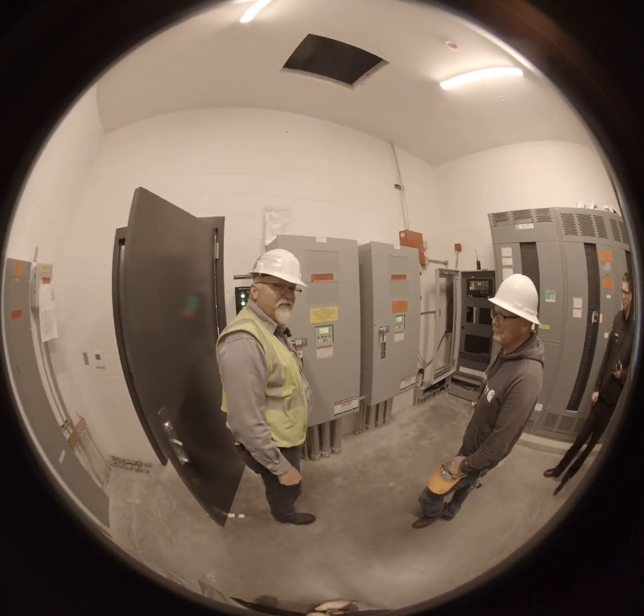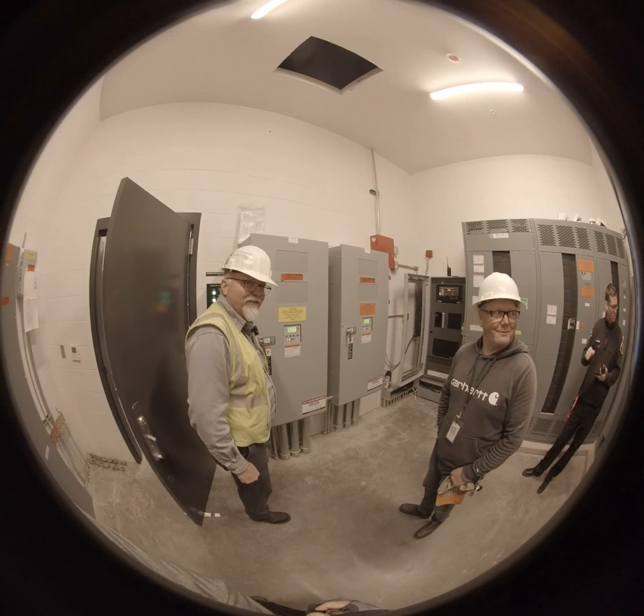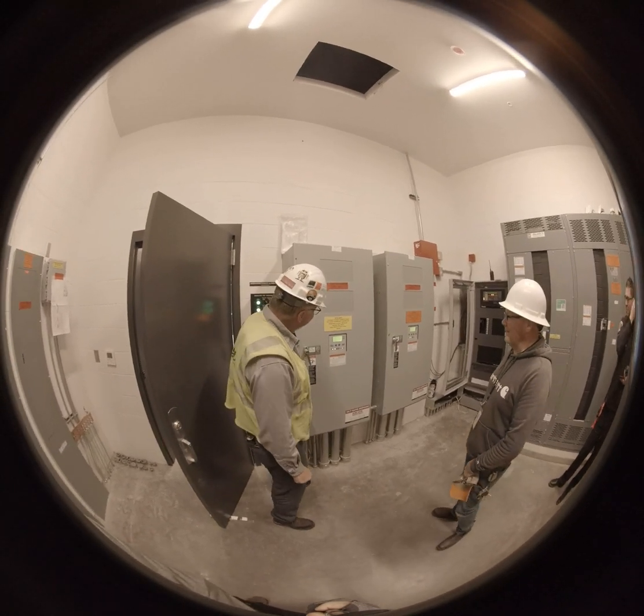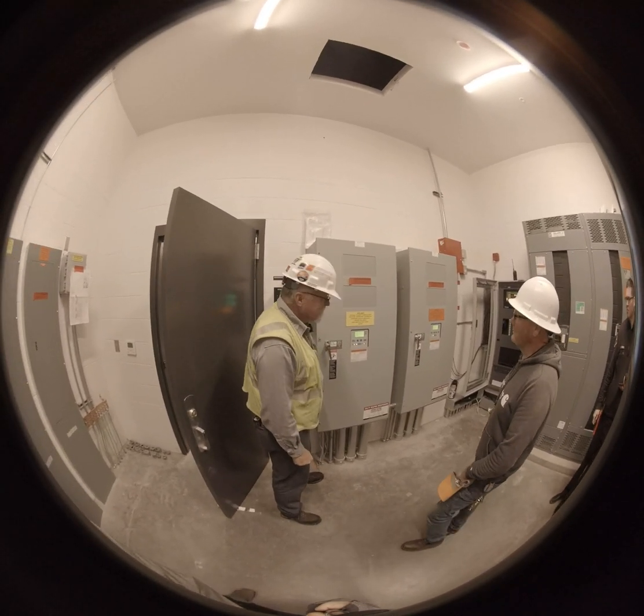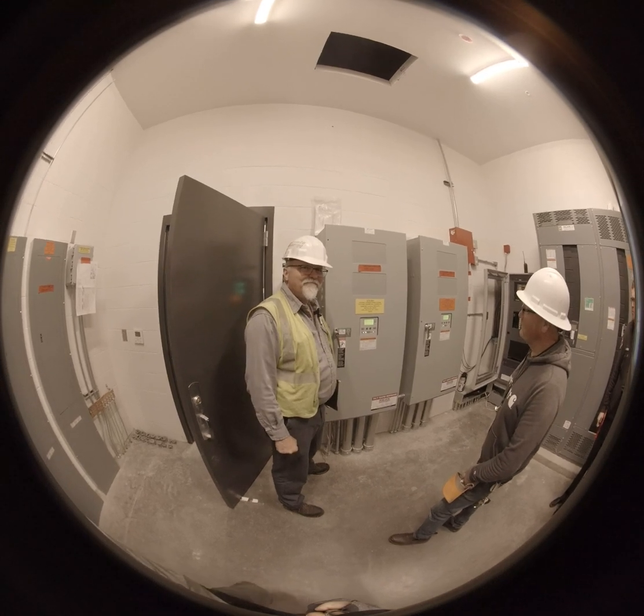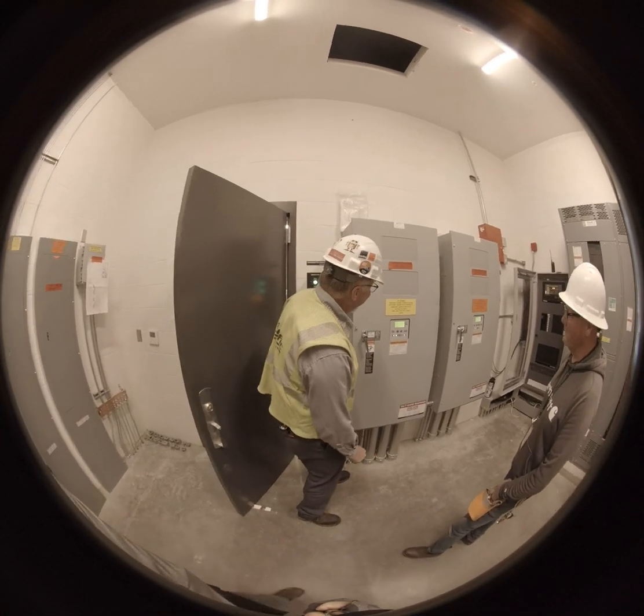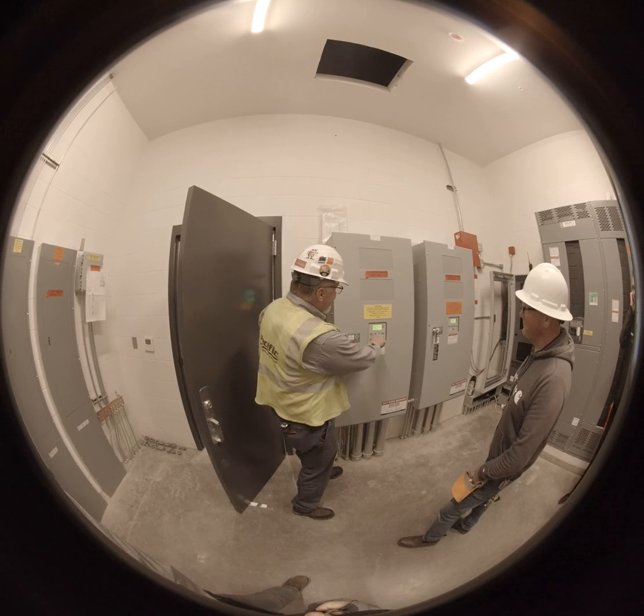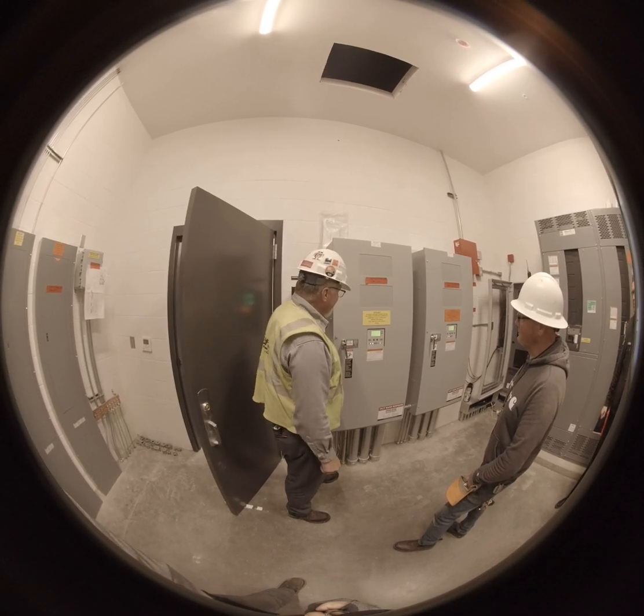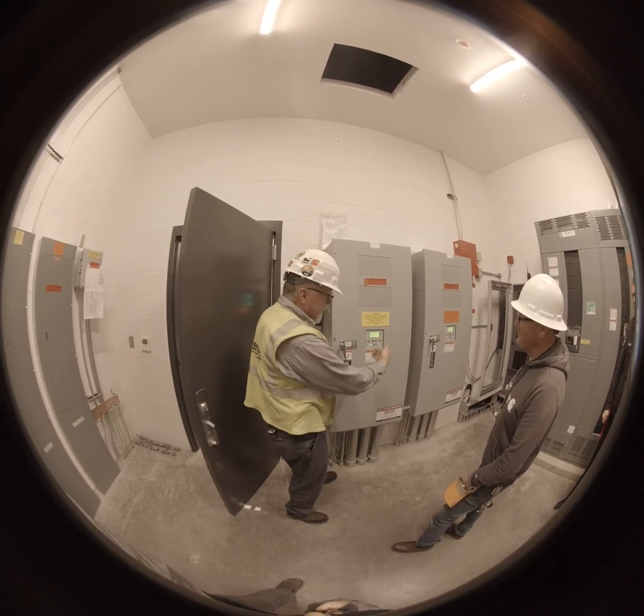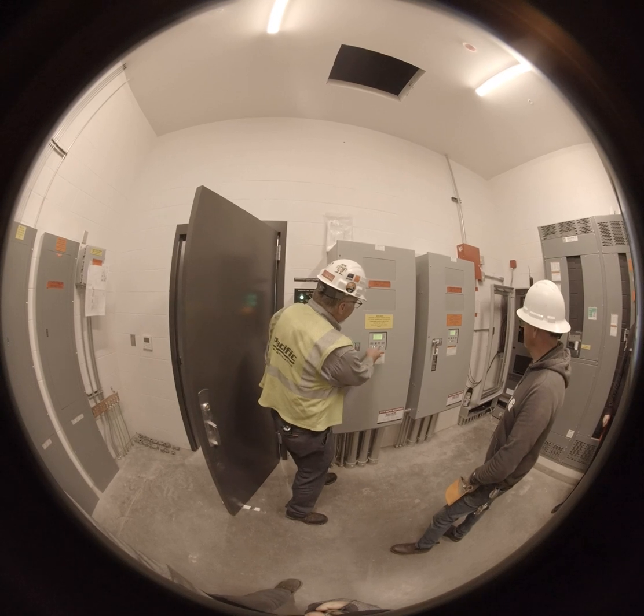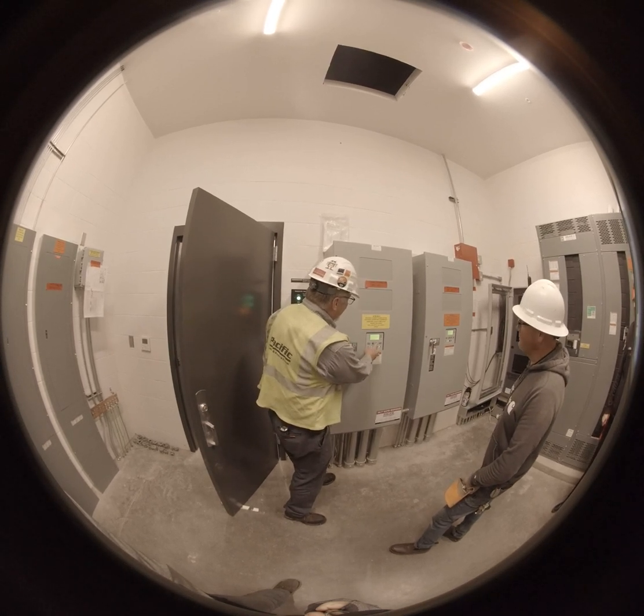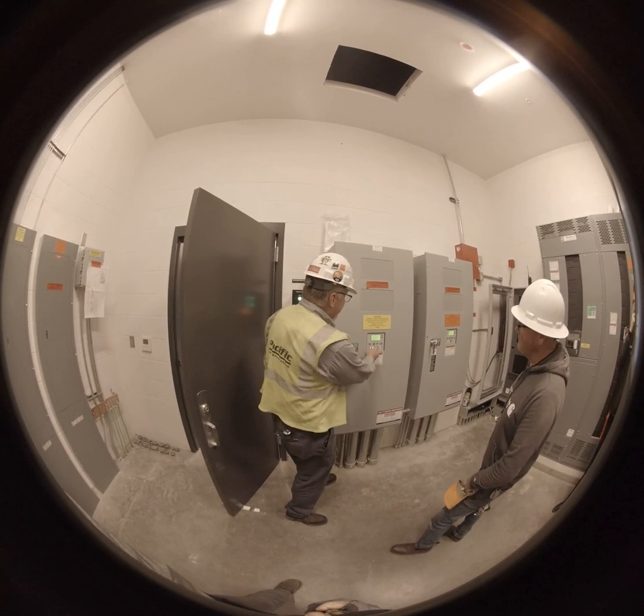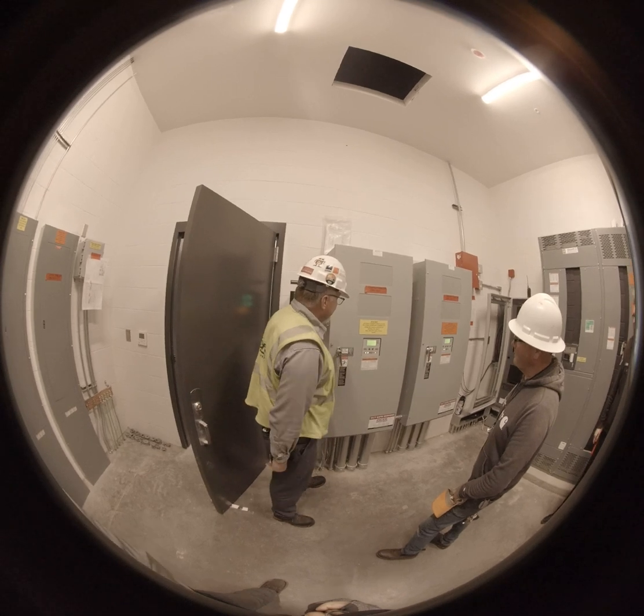Not too bad, Justin. You did okay on your voltages here. Yep, that's all PUD. So you can see this generator is still running. We're matched pretty close to the generator voltage. It should be shutting down here momentarily. Okay. No active alarms. Then it goes back to the beginning.